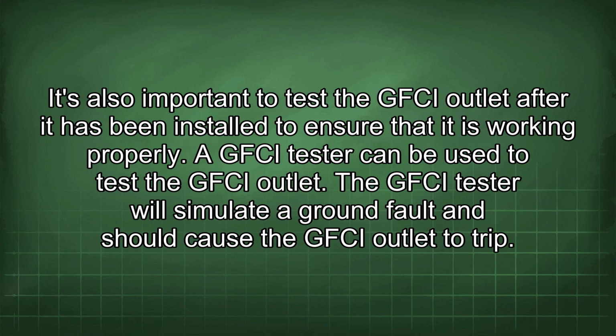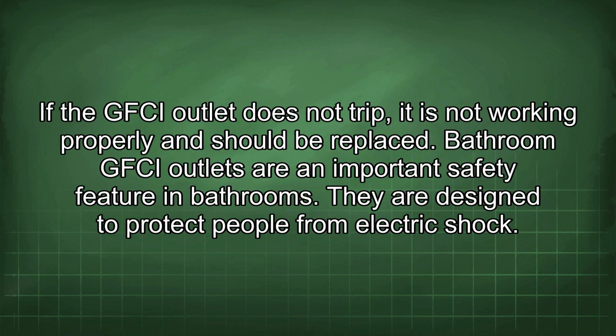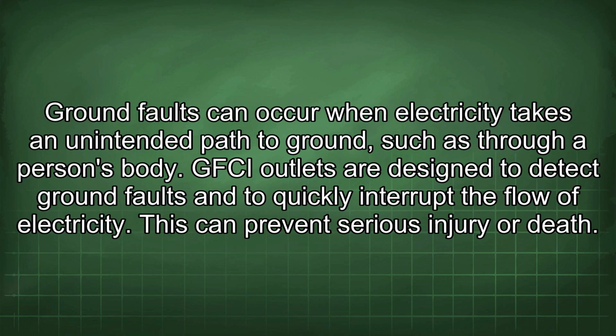It's also important to test the GFCI outlet after it has been installed to ensure that it is working properly. A GFCI tester can be used to test the GFCI outlet. The GFCI tester will simulate a ground fault and should cause the GFCI outlet to trip. If the GFCI outlet does not trip, it is not working properly and should be replaced. Bathroom GFCI outlets are an important safety feature in bathrooms. They are designed to protect people from electric shock. Ground faults can occur when electricity takes an unintended path to ground, such as through a person's body. GFCI outlets are designed to detect ground faults and to quickly interrupt the flow of electricity. This can prevent serious injury or death.